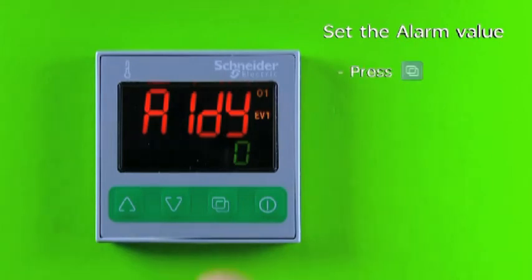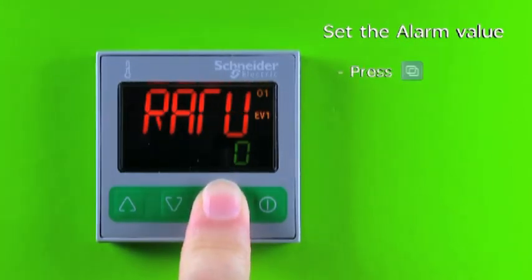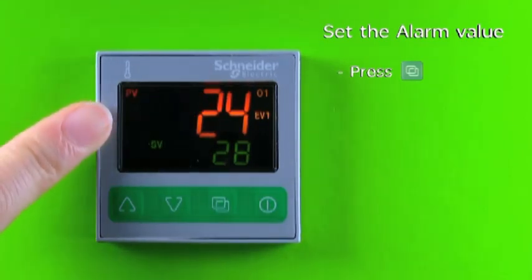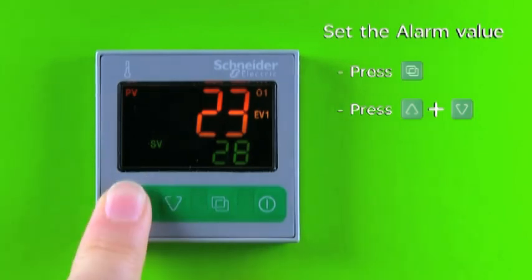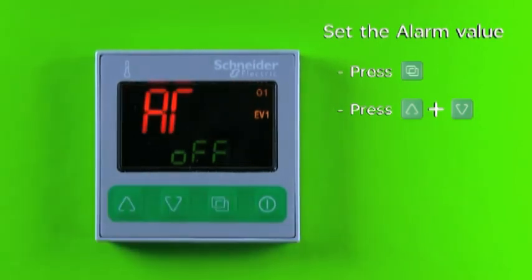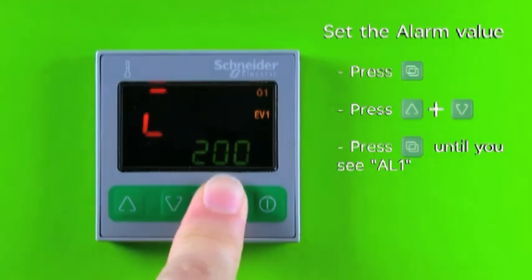Press and hold the page key for 3 seconds to return to PVSV display. Press and hold the increase key and decrease key at the same time to enter the subsetting mode. The display will show AT. Press and release the page key several times until the display shows AL1.